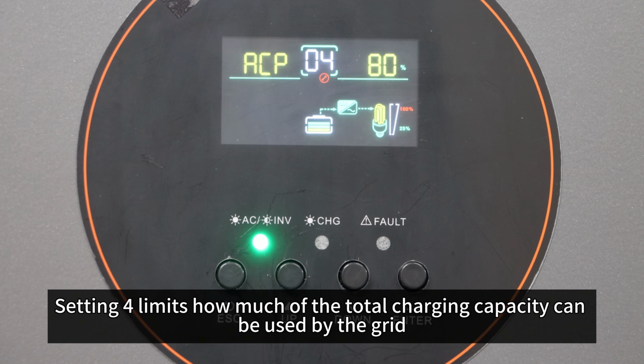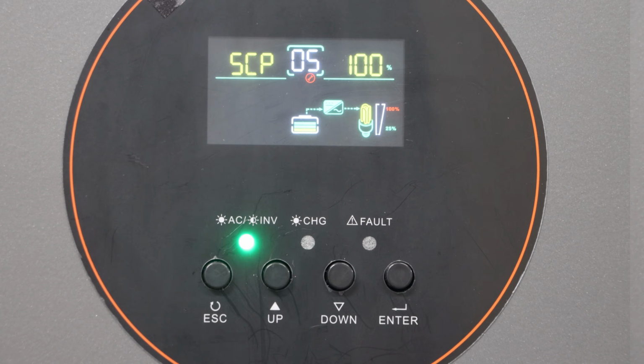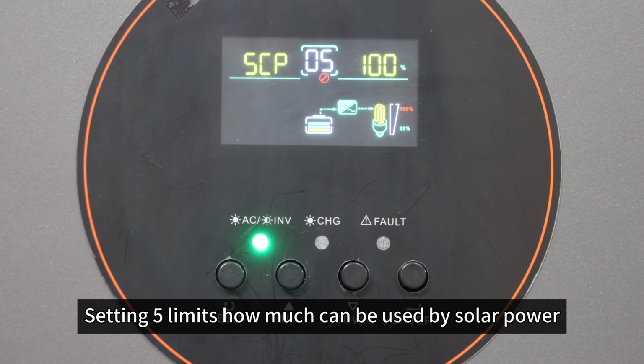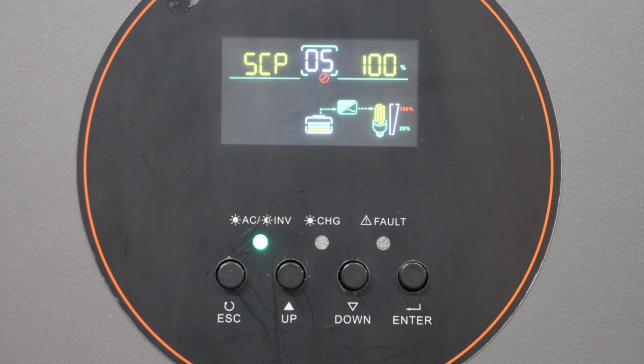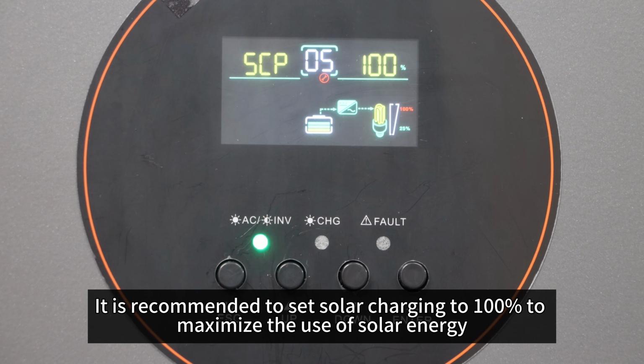Setting 4 limits how much of the total charging capacity can be used by grid. Setting 5 limits how much can be used by solar power. It is recommended to set solar charging to 100% to maximize the use of solar energy.